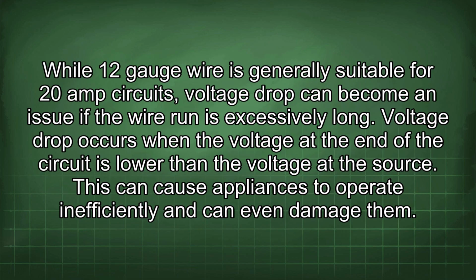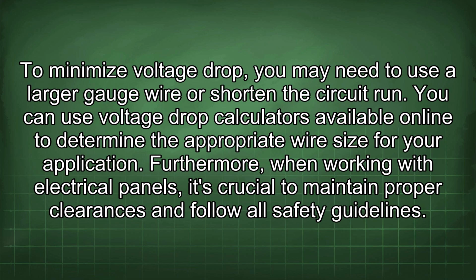While 12-gauge wire is generally suitable for 20 amp circuits, voltage drop can become an issue if the wire run is excessively long. Voltage drop occurs when the voltage at the end of the circuit is lower than the voltage at the source. This can cause appliances to operate inefficiently and can even damage them. To minimize voltage drop, you may need to use a larger gauge wire or shorten the circuit run. You can use voltage drop calculators available online to determine the appropriate wire size for your application.